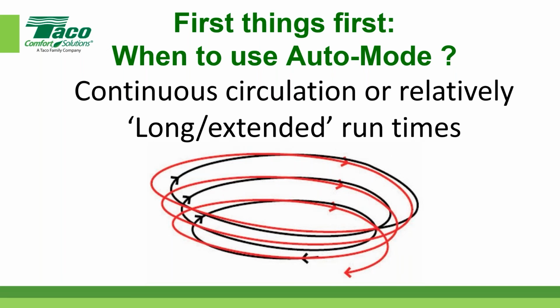So with these long or extended run times, the algorithm of the circulator has the ability to make some good decisions based on seeing flows increase and decrease and head increasing and decreasing. So it can gather enough information, being a delta P circulator, that it can make decisions to not only slide up and down a fixed proportional run, the operating range, but it can now decide whether it's going to step up and down the rungs of the ladder. So within those shaded areas, those wedges of operating condition, you actually have little adjustments in the pitch of those. And I like to call them steps of a ladder or rungs on a ladder.